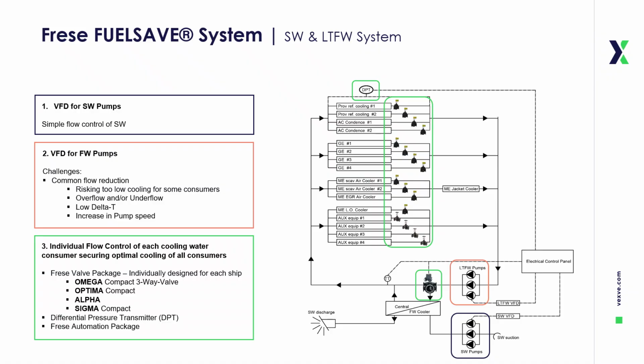The Frese FUELSAVE solution is designed to optimize both seawater and low-temperature freshwater cooling systems. Its primary goal is to ensure efficiency, reliability, and fuel savings. The system consists of 3 steps. 1. Introduction of variable frequency drive for the seawater pumps. 2. Introduction of variable frequency drives for the low-temperature freshwater pumps.